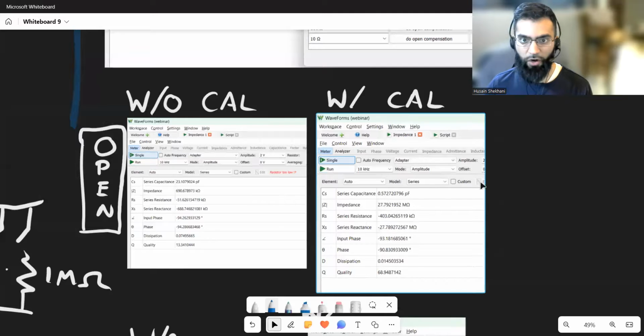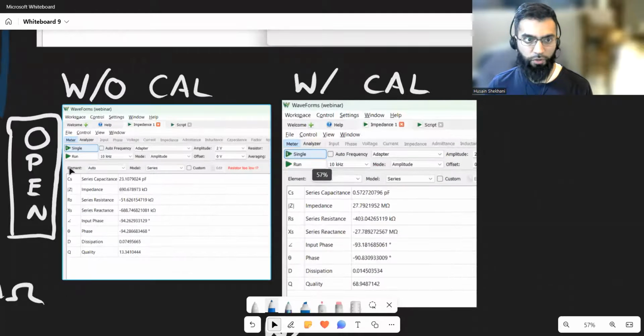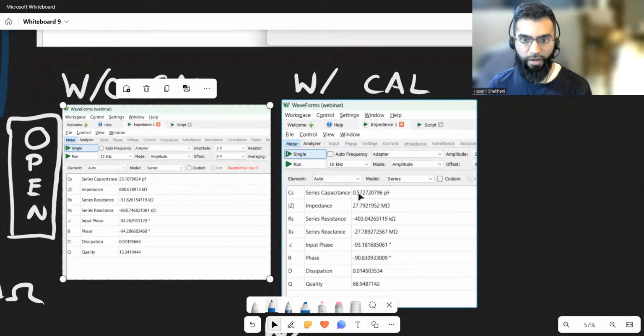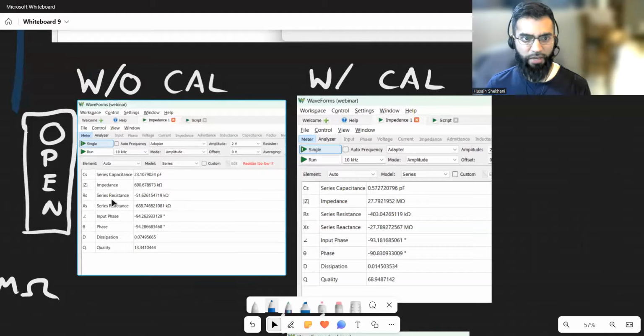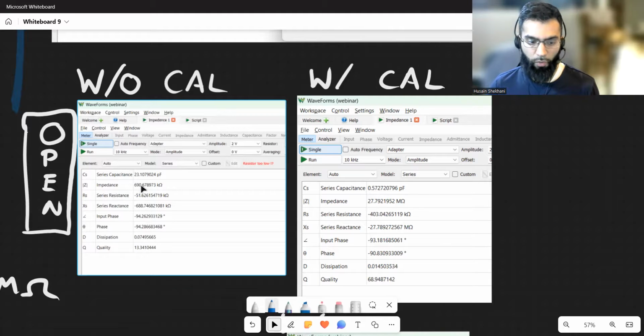So we have both LCR and impedance measurements that you can do. Without calibration, the LCR mode was showing 23 picofarads of capacitance. After calibration at 10 kilohertz, it was showing 0.5 picofarads. And just to note, sometimes it's not really necessary to do compensation, when you are not measuring anything where that series capacitance would impact your measurement. Sometimes calibration can get tricky, or it's another step. So you should evaluate whether you need to do it for the particular device you're working on.